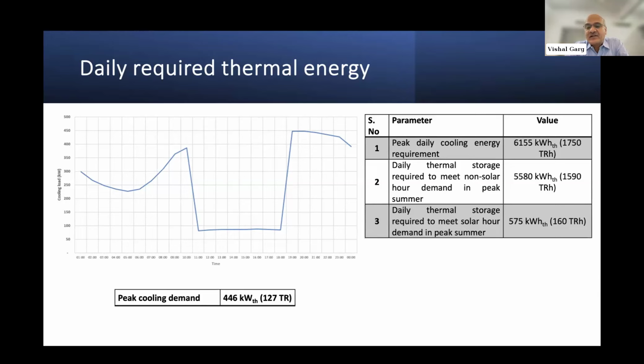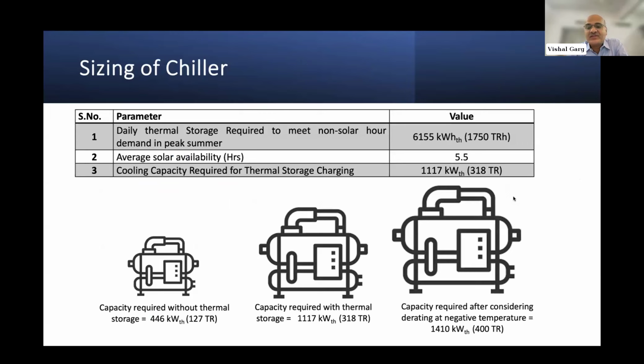Out of this 1750 ton hour, the consumption in the evening and the night time, we are calling that as non-solar hours, that is about 11 hours, is about 1600. And in the daytime, the consumption is about 150 ton hour. So the idea is how do we shift this 1600 ton hour from nighttime to daytime by charging thermal storage? So if we go for business as usual, then we need 127 ton.